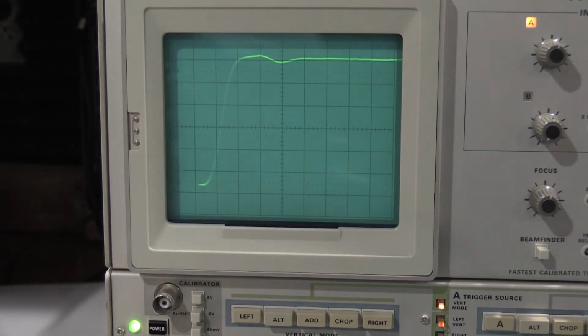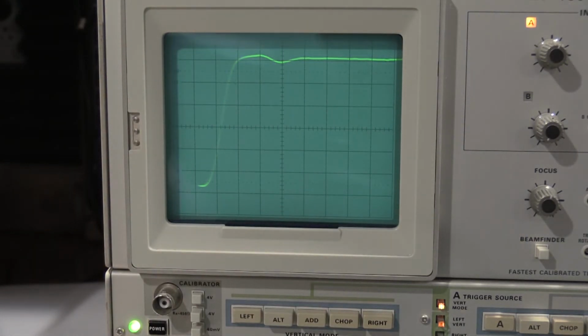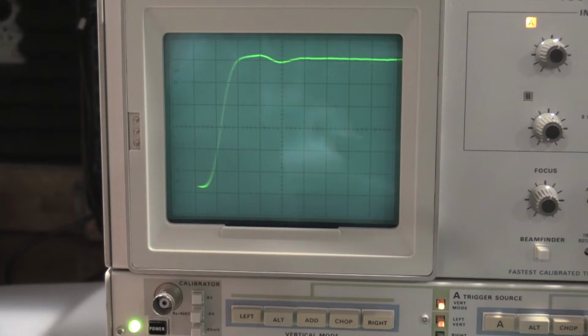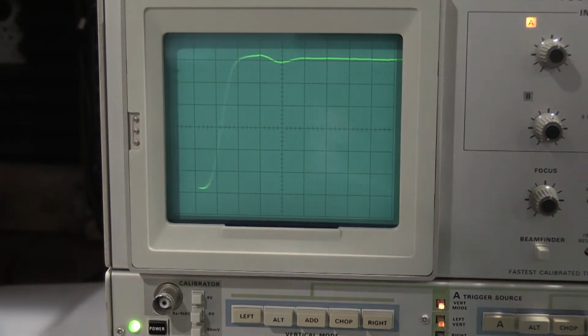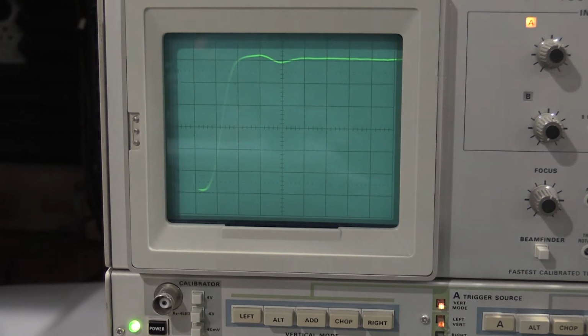So that'll check the plus side. I'm going to check the minus side, which is doing exactly the same thing. Just run it through the attenuator, see what it looks like. But one thing to know is on the minus side of things, you want to use a fast falling edge, not a fast rising edge. It's very easy on the PG506 to plug it into the wrong socket and get the wrong edge for the adjustment that is being done. And you can chase your tail for a couple of days if that happens. Don't ask me how I know.